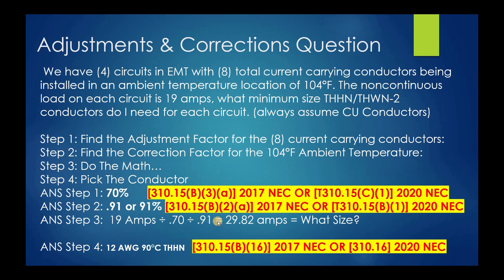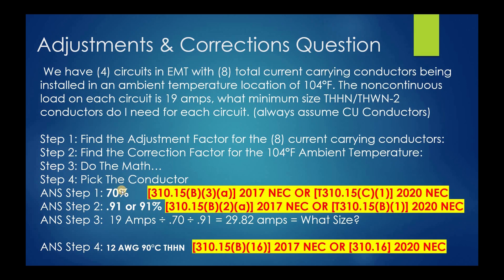Now let's verify our work using multiplication. We selected 12 gauge, which is rated for 30 amps in the 90-degree column. Multiply 30 amps × 0.70 × 0.91, and that gives us 19.11 amperes. Can a conductor good for 19.11 amps handle 19 amps of non-continuous load? Absolutely. I'll protect that 12-gauge conductor with a 20-amp overcurrent device in accordance with 240.4(D) — the small conductor rules. We're not talking motors or HVAC here with allowances under 240.4(G) — just the basics.